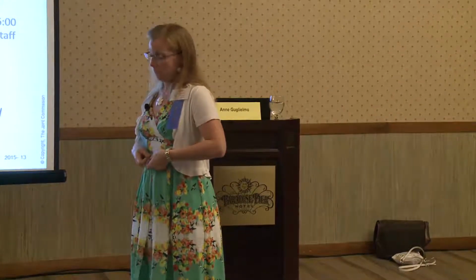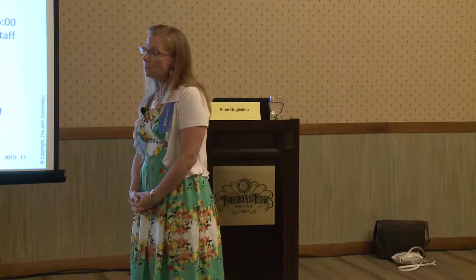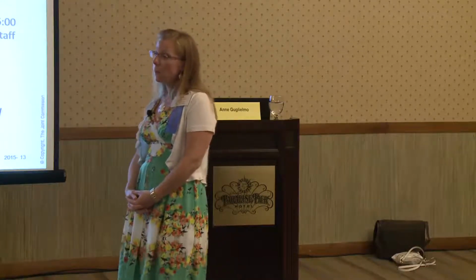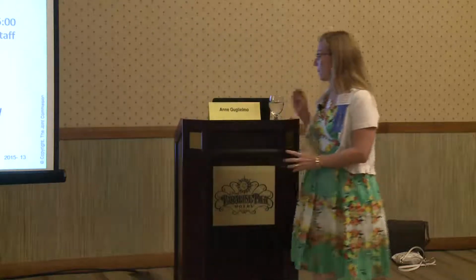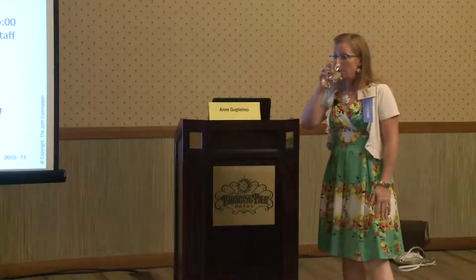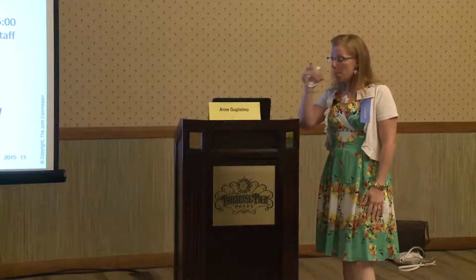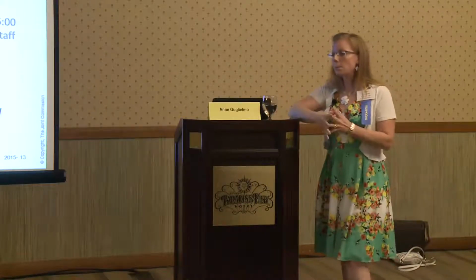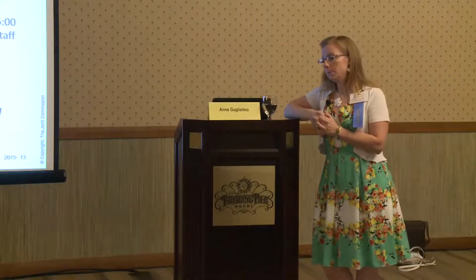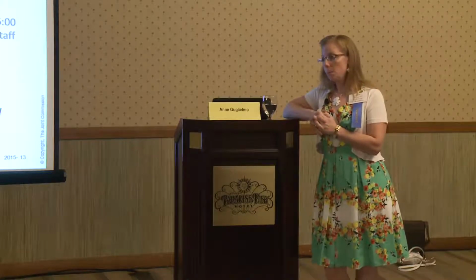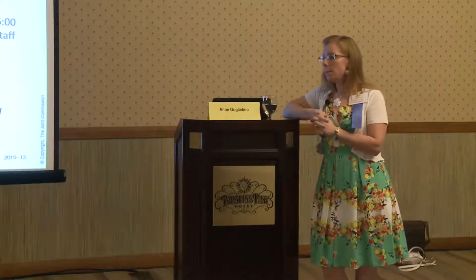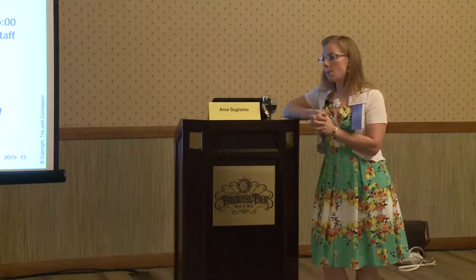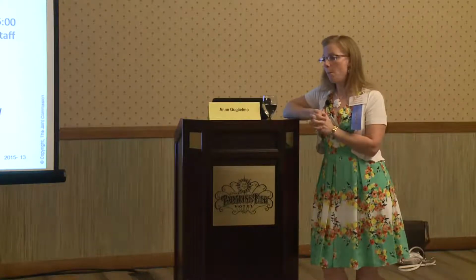I actually sent a response up to George Mills about this, did a bunch of research in NFPA 72 and the history of the old code in NFPA 101 regarding silent fire drills. There are fire alarm panels that can't be silenced — correct, and the intent put back in 2000 was that some panels couldn't be silenced. The purpose of the fire drill is for staff education, not testing of the equipment; equipment testing is covered by different EP standards. It was only recently, when Joint Commission started inspecting this, that it came up — most hospitals I was aware of until recently were doing silent fire drills.